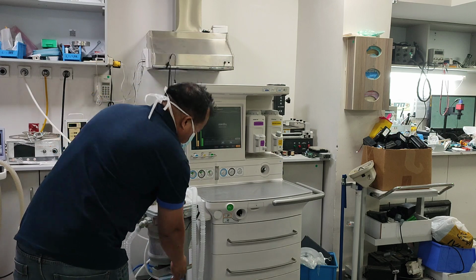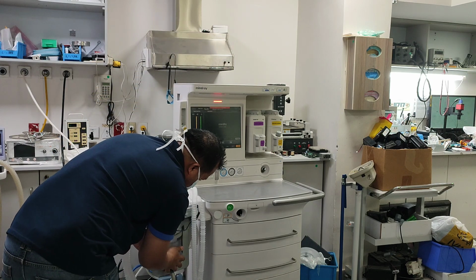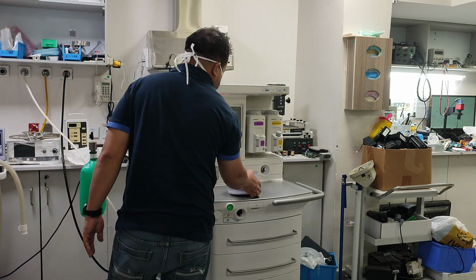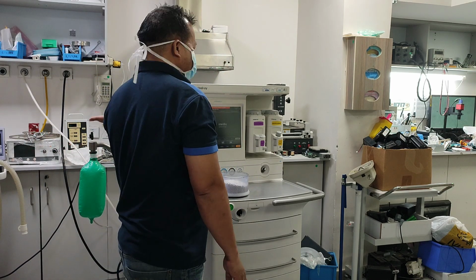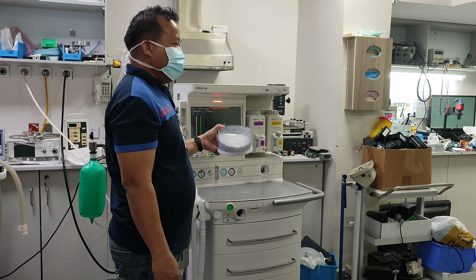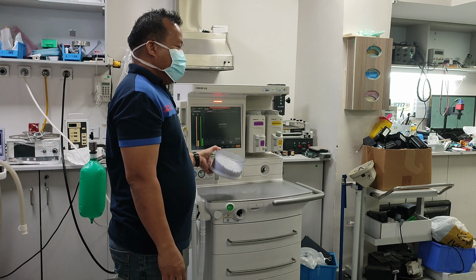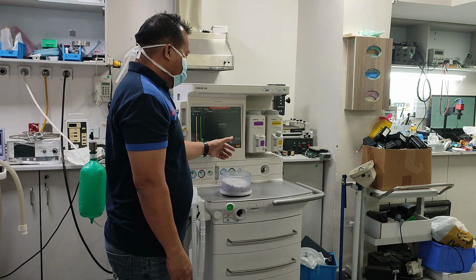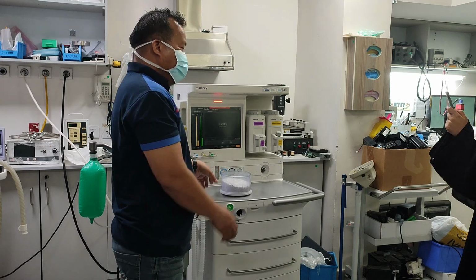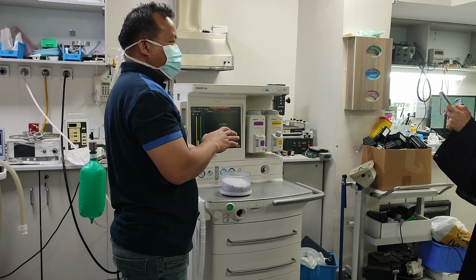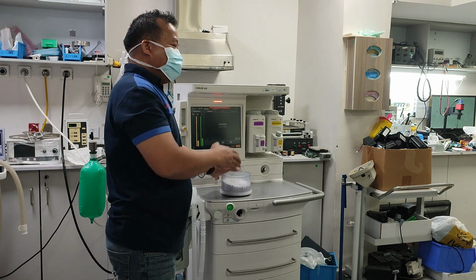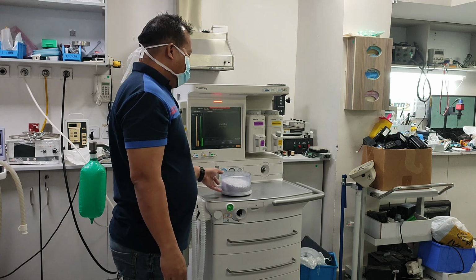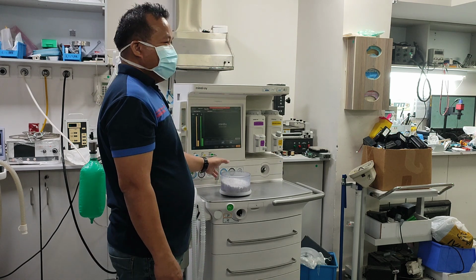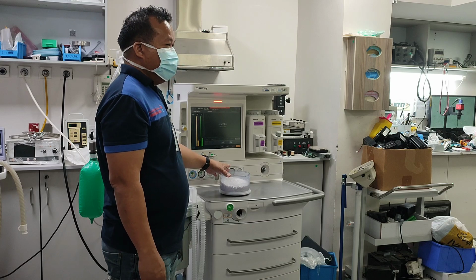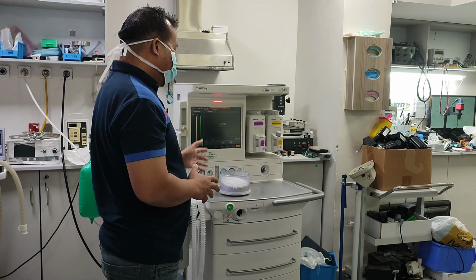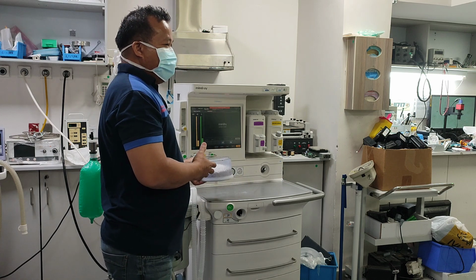We have also here, this one, which goes to the line. This one is not in the ventilator. This is the CO2 absorber. When the patient inhales and exhales, the gas goes through the line and comes back to the patient, meaning the carbon dioxide is already filtered here and it is cleaned before going again to the patient. You cannot use the anesthesia machine without this. This is very important for the patient because the carbon dioxide would suffocate the patient. So the purpose of this one is to filter the carbon dioxide of the patient during ventilation.